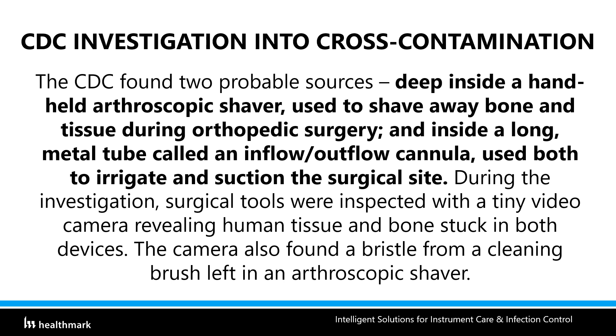So in this case, since the shaver was an FDA regulated item, the CDC contacted the FDA, and the FDA at that time sent an email or letter to all the hospitals at the University of Michigan. We received an email saying that the FDA has become aware of an event in which tissue remained within certain arthroscopic shavers, even after following manufacturer recommended cleaning. Additionally, reports submitted to the FDA suggest that the tissue retained was not evident to the naked eye, and multiple manufacturers sent letters to the users or hospitals saying to make sure that you're following the IFU for cleaning.